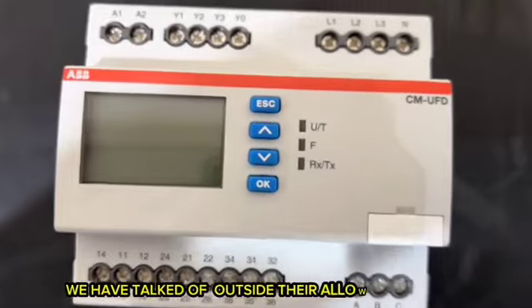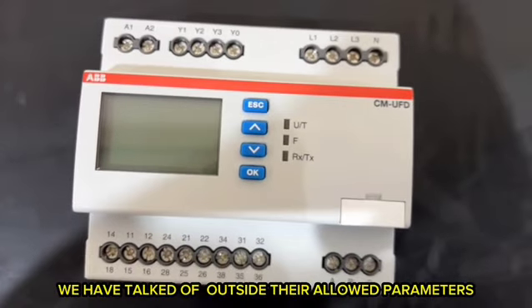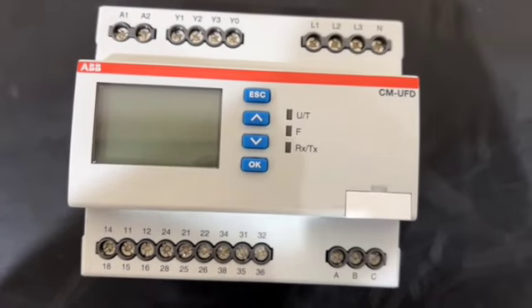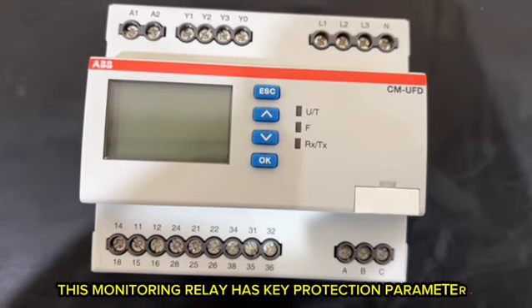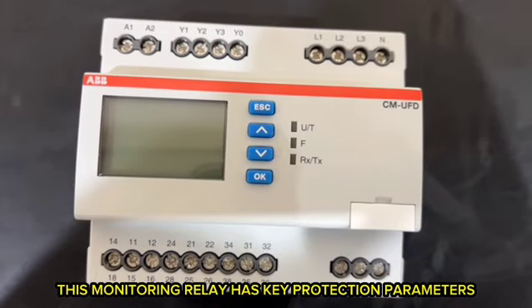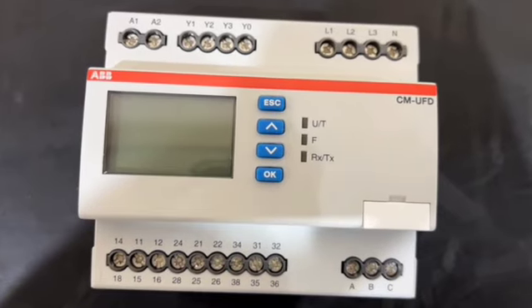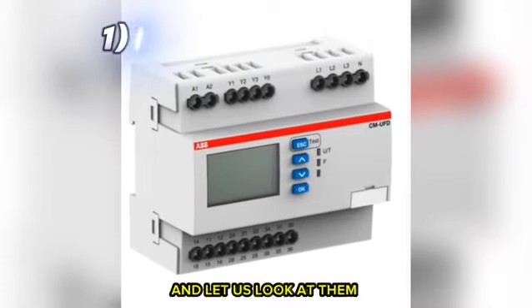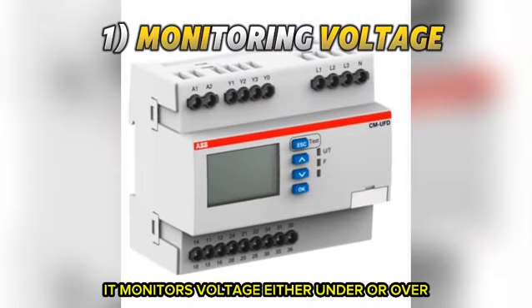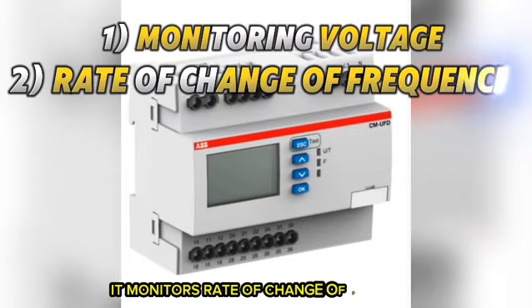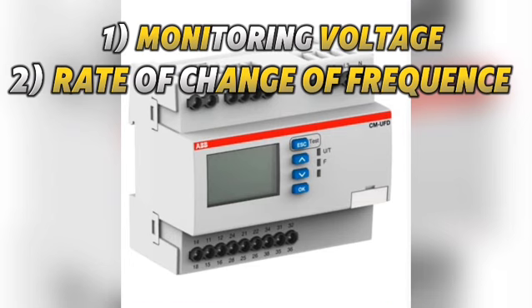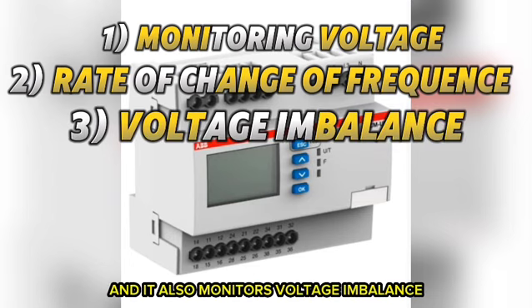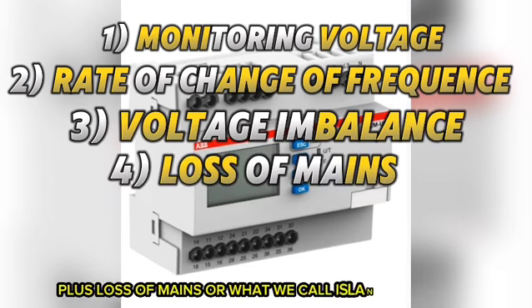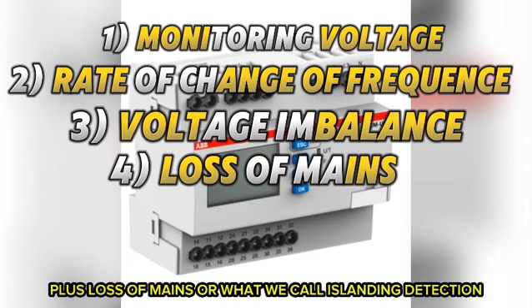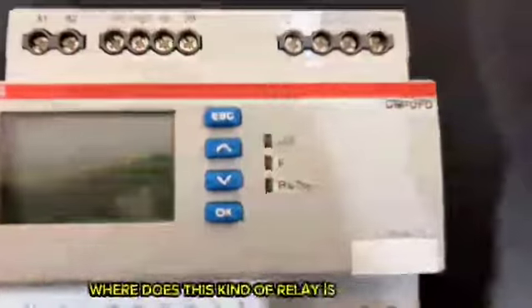So we have talked of outside the allowed parameters. What do we mean? This monitoring relay has key protection parameters and let us look at them. One, it monitors voltage, either under or over. It monitors rate of change of frequency, and it also monitors voltage imbalance plus loss of mains, or what we call islanding detection. Where is this kind of relay applied or used?